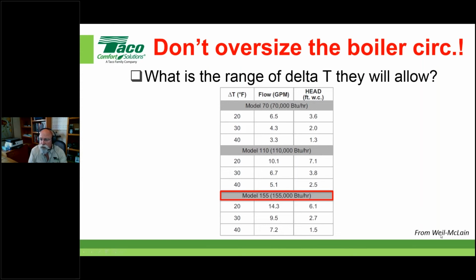You can see that down here, and this is what their chart shows for their condensing product. And my point is, I'm still emphasizing the fact that you don't want to oversize the boiler circulator. And again, these manufacturers will make it even easier for you to do this if you just read the manual, okay? But I'm going to generalize some things as well because you might not have the manual in front of you, or I might be able to emphasize the concept a little more here. So what is the range that the boiler manufacturer will allow? The concept here, folks, is go as far as they will allow you in writing.